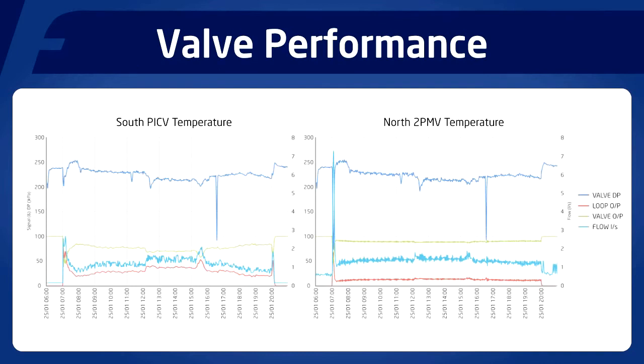We also collected data of the pressure drop across the control valve, which is the dark blue line and can be read against the left-hand y-axis. We can see that this varied between around 200 and 250 kPa on this particular day. However, we also can see that on the light blue line, which is the flow rate through the valves and can be read across the right hand y-axis, that when the system switched on at 7 o'clock in the morning, and of course the air had to be cooled quickly down from a higher temperature, that the flow through the pressure independent control valve spiked up to around 2.5 litres per second, but was still regulated.